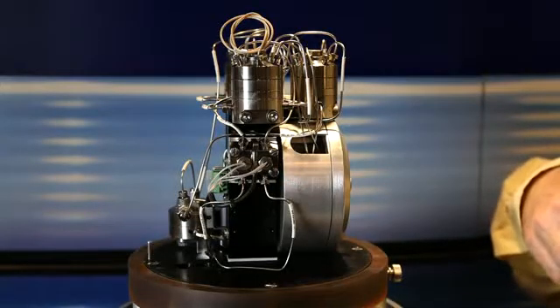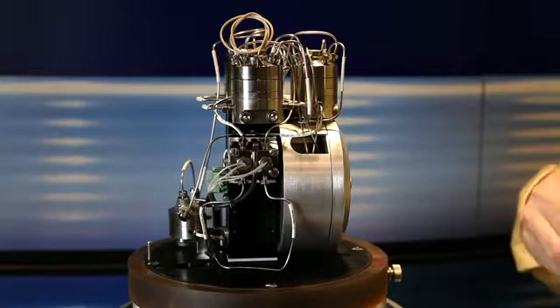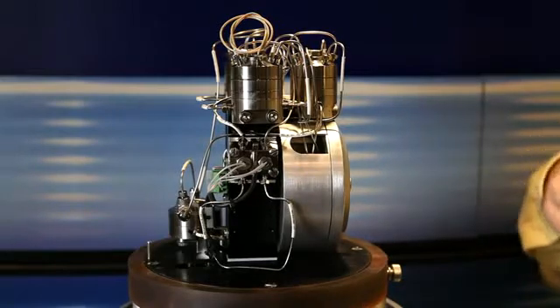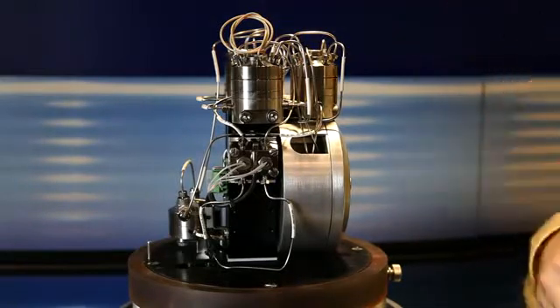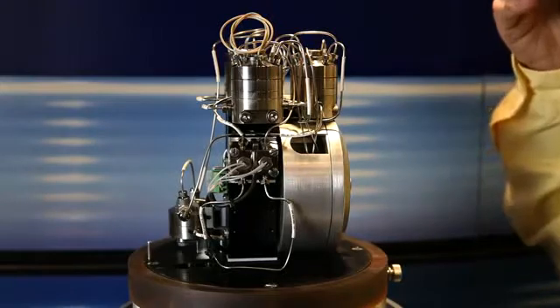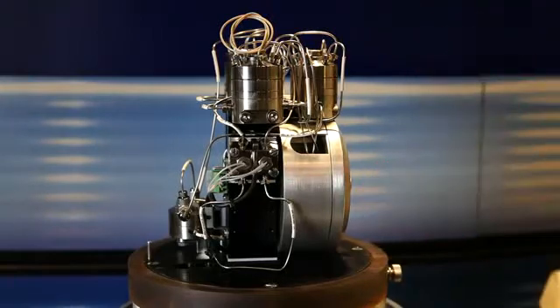And the 700 XA expands our analytical capabilities by using up to four six port or ten port analytical valves and micropacked or capillary columns.